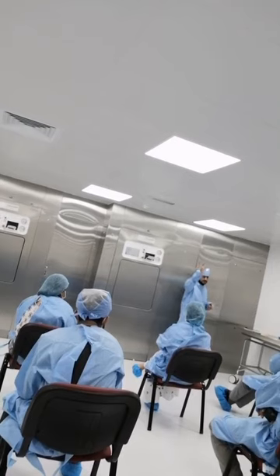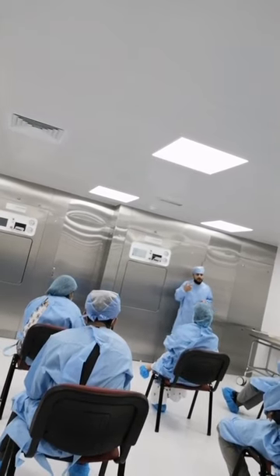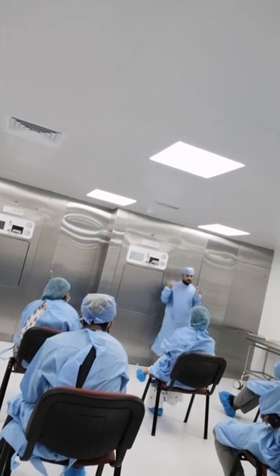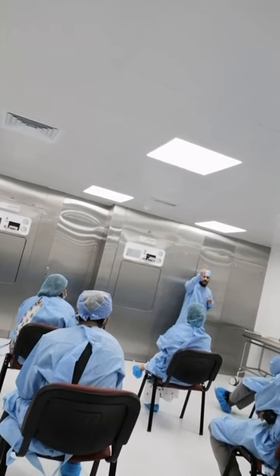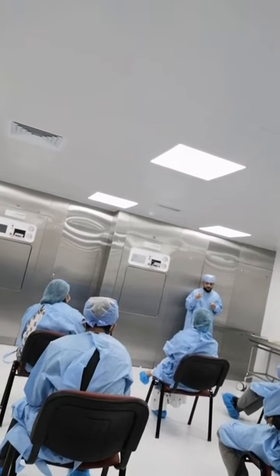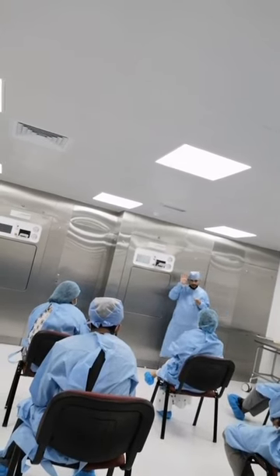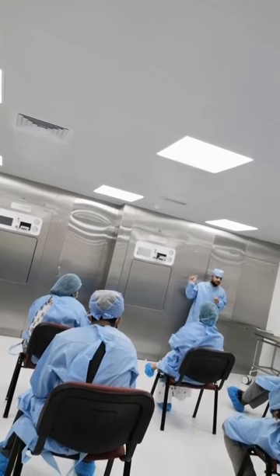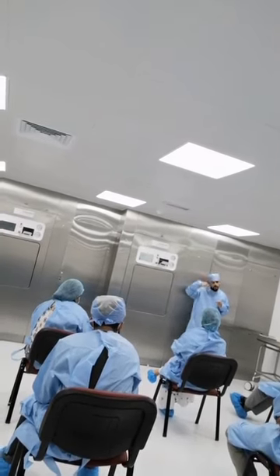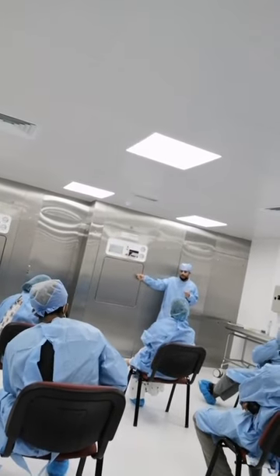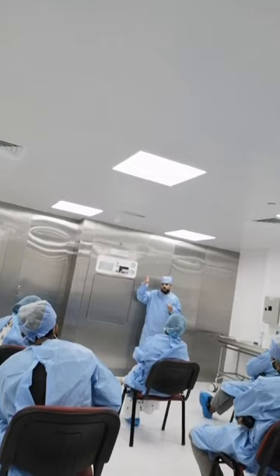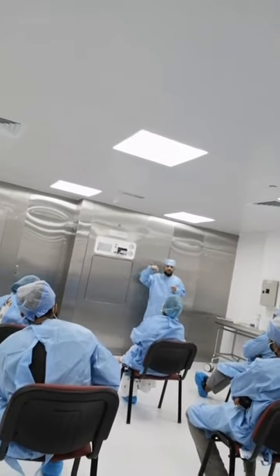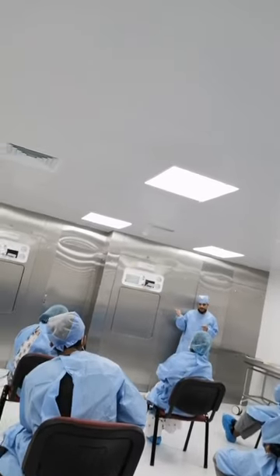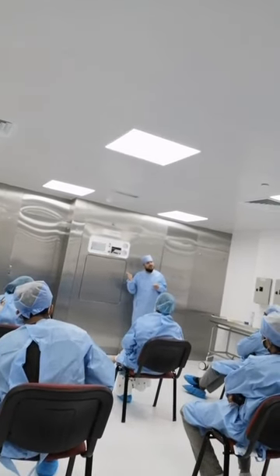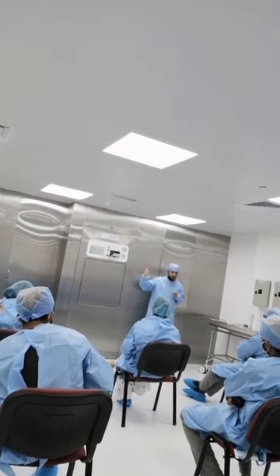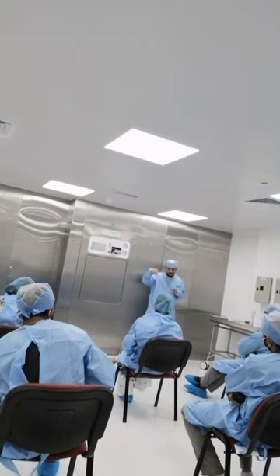But if you have machines, washer and sterilizer, which can process the full cycle in 2.5 hours instead of 4 hours, you can serve double the patients, take double the money. Instead of each OR taking 4 patients per day, they can take 6 and 8. Okay? And put into consideration also the running cost of the machine, consumption of water and consumption of electricity. And it is one of the least consumption of water in the business. So yes, we are expensive, I'm not saying no. We're facing a very hard time these days because of our price, but please look at the most important parameter.